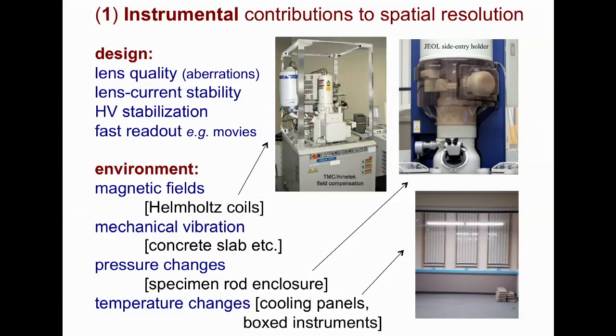Mechanical vibration must be low, and this is usually achieved by installing the instrument on a thick concrete slab, possibly with an anti-vibration mounting. Changes in air pressure can affect image stability because most TEMs use a side entry specimen holder that is vulnerable to pressure changes. At the top right here, you see a plastic enclosure being used to protect the specimen region of a TEM. Temperature changes must also be minimized, usually by using low airflow in the microscope room and water-cooled panels on the walls. It's now common to see expensive TEMs enclosed in a metal box, which probably helps to reduce several of the above problems.